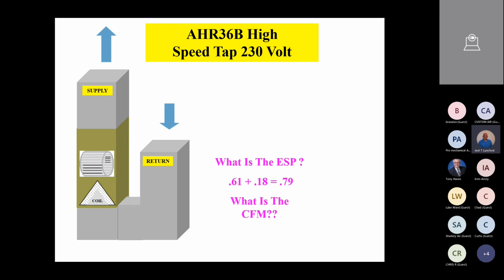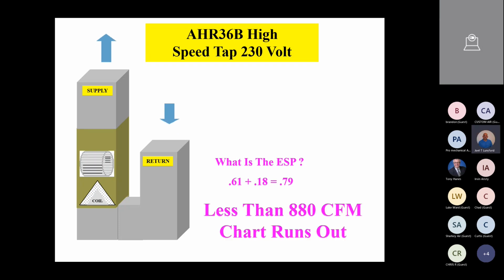So the 0.79, as we take a look at our airflow chart, an AHR 36B on high speed tap, 230 volt, what is our CFM? Does anybody have the CFM off that chart at 0.79? So we know something. We know that it's going to be less than 880 CFM because the chart runs out. It's off the chart.